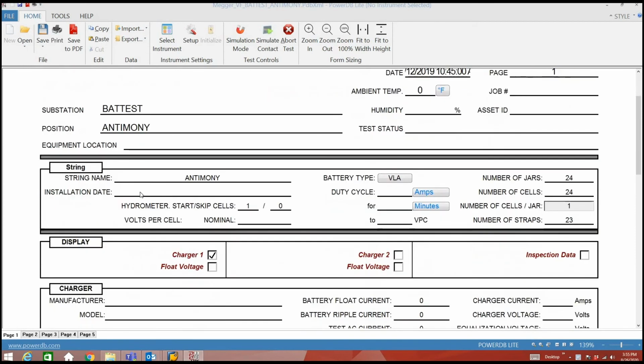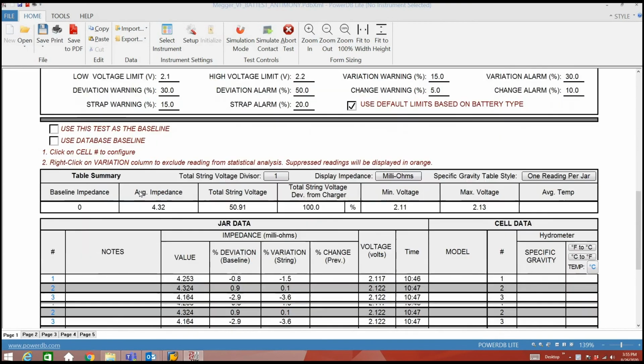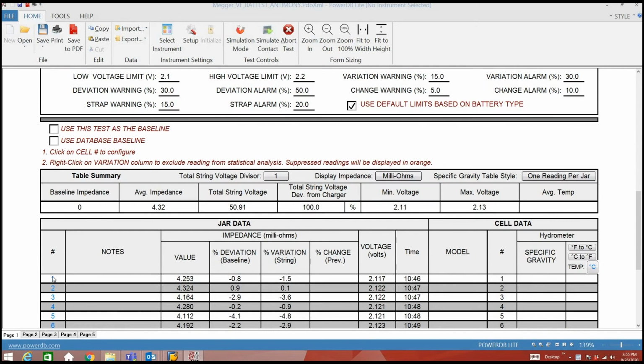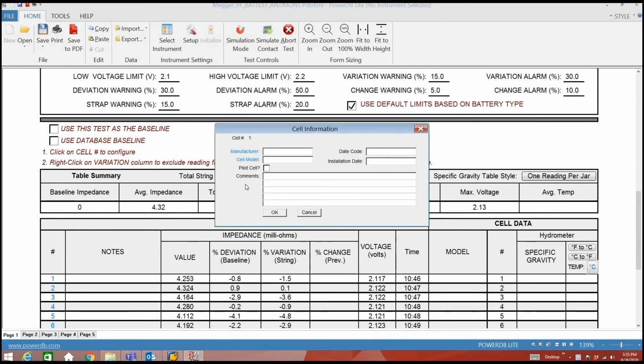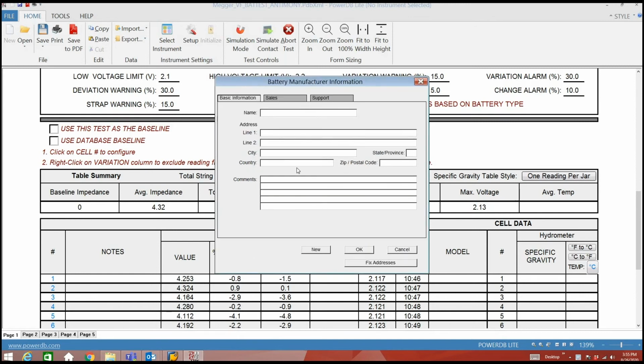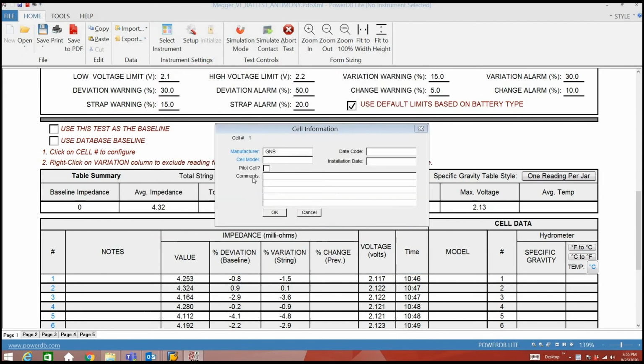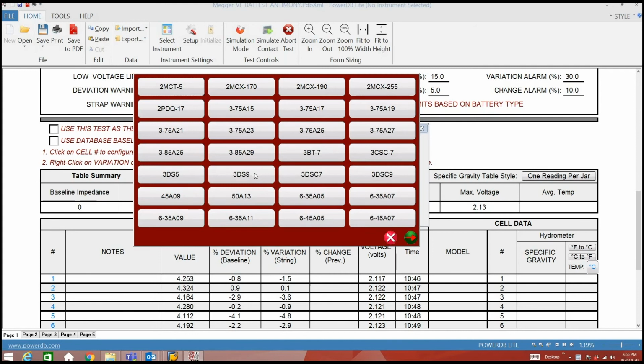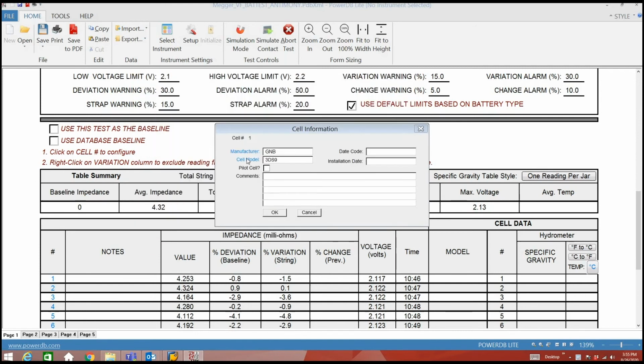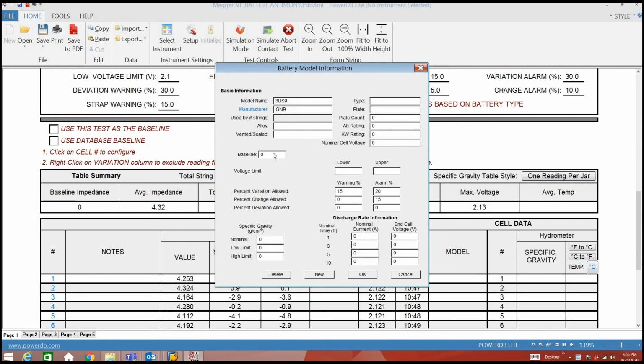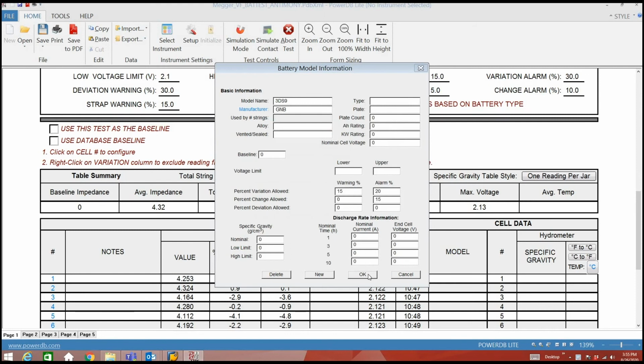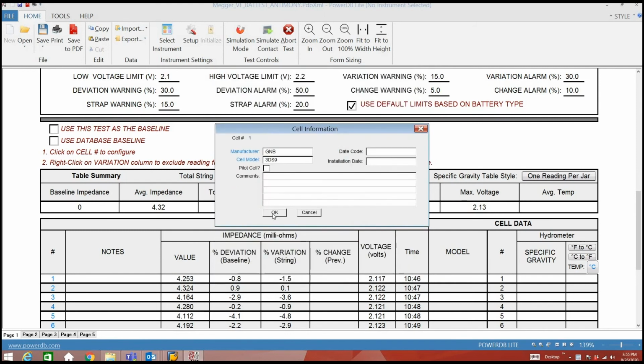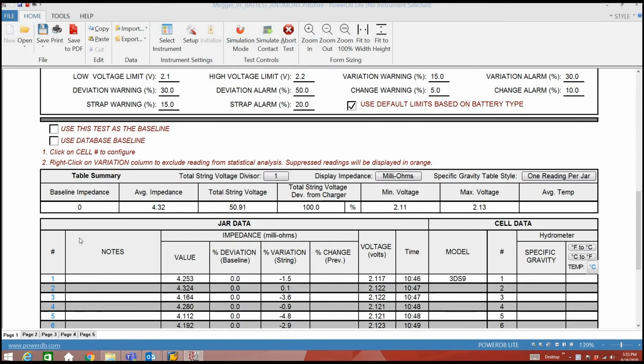To enter a baseline value, there are several ways this can be done. If I already know the baseline value that I wish to use, then I can click on the cell number. I can then click on the manufacturer and enter a manufacturer's name, or I can click on the field and select from a list of manufacturers. I can then click on the cell model field and select from a list of cells, or click on cell model, and I can then enter a new cell, and this is where I can enter the baseline value that I wish to use, as well as various limits. When complete, click OK. Then just click on Use Database Baseline to use this baseline value.